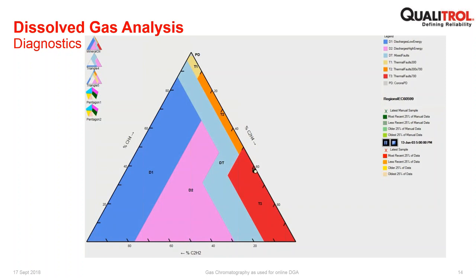So the Duval triangle number 1 was, as the name implies, the first one released, and it gives you a capability to look at diagnosis of your transformer on the basis of 7 different possible conditions. So they're shown in the top right hand side. The blue area is discharges of low energy. The pink is discharges of high energy. Light blue, mixed fault, etc. So as the coordinate points of those 3 gases, methane, ethylene, and acetylene, where they intersect, indicate the nature of a fault. In the case of Duval triangle, they don't necessarily indicate the presence or absence, because those 3 points will always intersect somewhere, and therefore there are further considerations over and above the intersecting points.